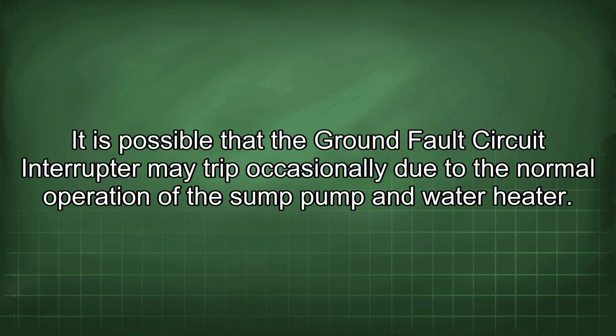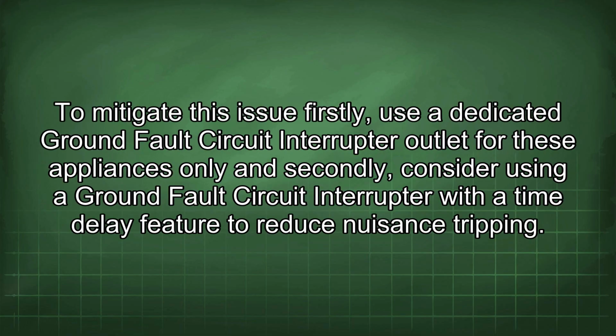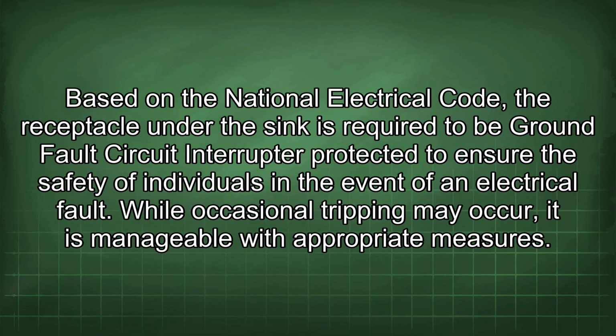It is possible that the ground fault circuit interrupter may trip occasionally due to the normal operation of the sump pump and water heater. To mitigate this issue, firstly, use a dedicated ground fault circuit interrupter outlet for these appliances only, and secondly, consider using a ground fault circuit interrupter with a time delay feature to reduce nuisance tripping. Based on the National Electrical Code, the receptacle under the sink is required to be ground fault circuit interrupter protected to ensure the safety of individuals in the event of an electrical fault. While occasional tripping may occur, it is manageable with appropriate measures.